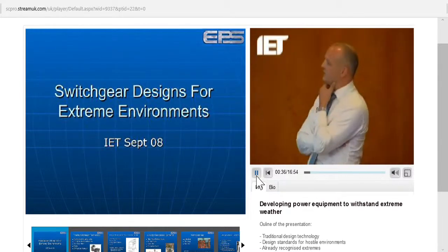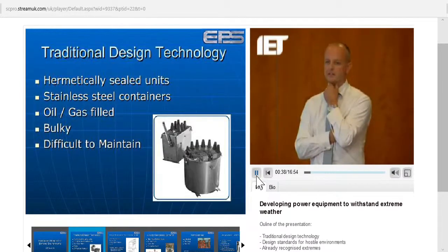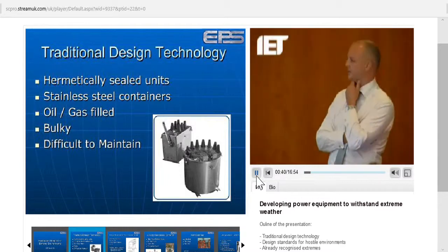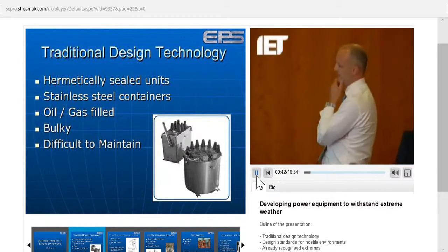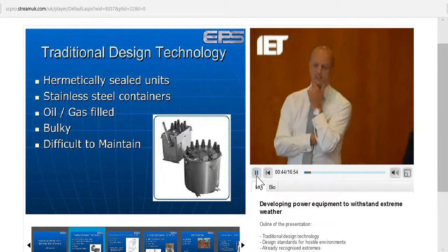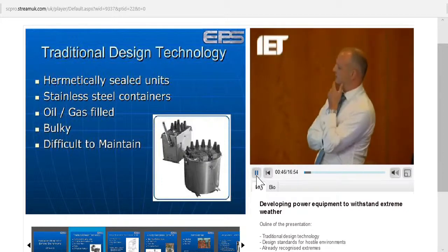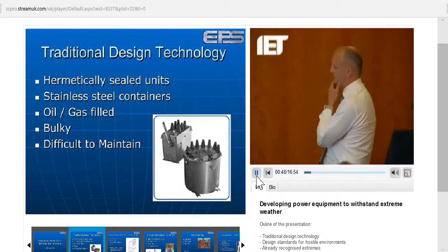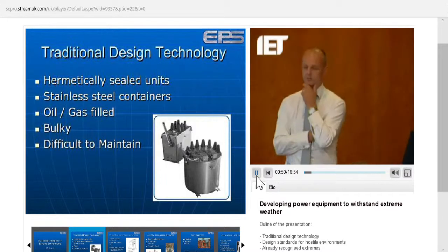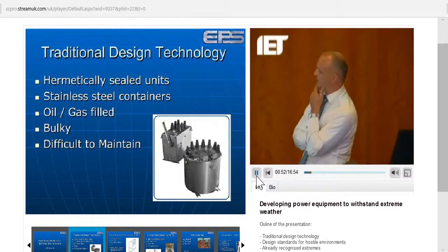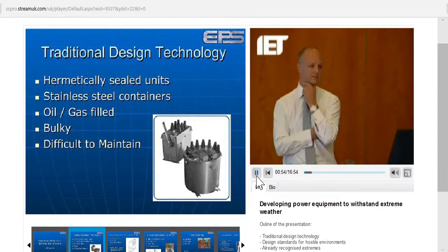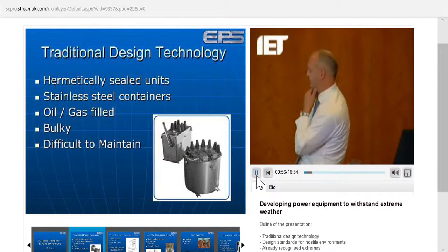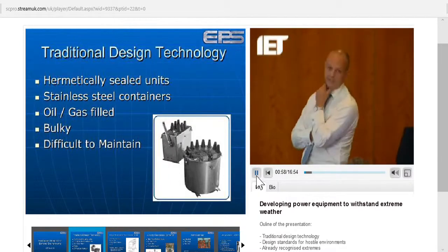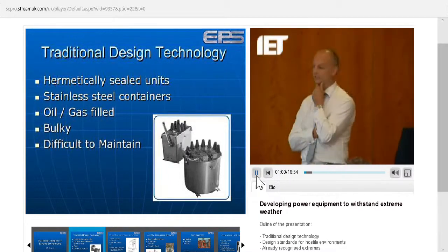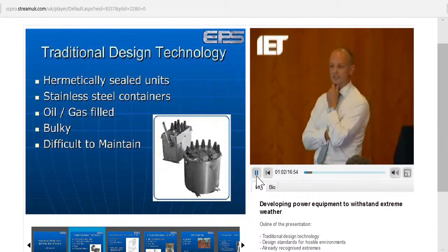Traditional technology currently used in flood-proof switchgear tends to look like this: hermetically sealed units, stainless steel tanks. They'll have a tapered bushing on top to connect the cables, and generally they'll be filled with either oil or gas, SF6 gas. They're quite bulky, quite heavy, and difficult to maintain because they're designed to be sealed.